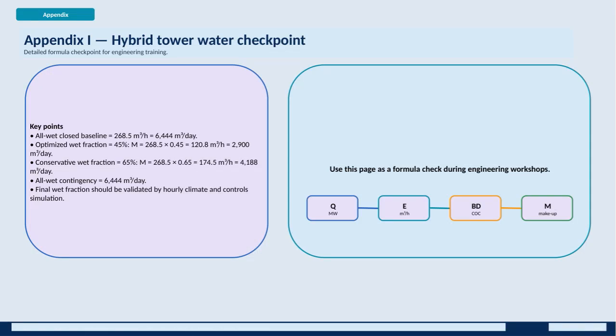This appendix section focuses on the hybrid tower water checkpoint, which is a detailed formula checkpoint designed specifically for engineering training. It is part of the broader training concept package related to the Batum Coastal Data Center's water supply system, including seawater reverse osmosis desalination, direct liquid cooling, and cooling tower integration. Key points to note here include the baseline all-wet closed system flow rate, which is 268.5 cubic meters per hour, or about 6,444 cubic meters per day.